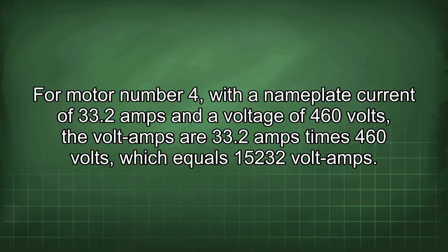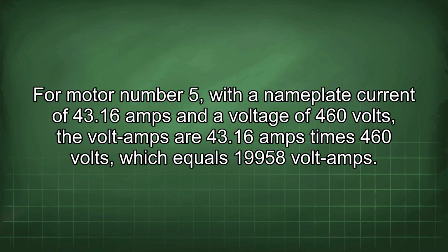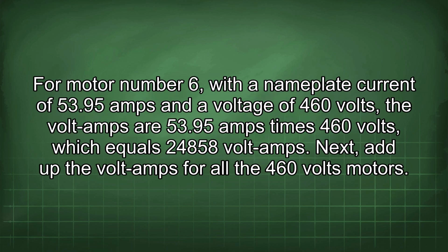Secondly, calculate the volt amps for each of the 460 volts motors. For motor number 4, with a nameplate current of 33.2 amps and a voltage of 460 volts, the volt amps are 33.2 amps times 460 volts, which equals 15,232 volt amps. For motor number 5, with a nameplate current of 43.16 amps and a voltage of 460 volts, the volt amps are 43.16 amps times 460 volts, which equals 19,958 volt amps. For motor number 6, with a nameplate current of 53.95 amps and a voltage of 460 volts, the volt amps are 53.95 amps times 460 volts, which equals 24,858 volt amps.